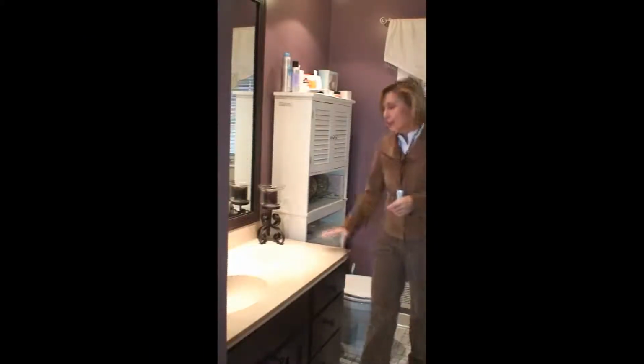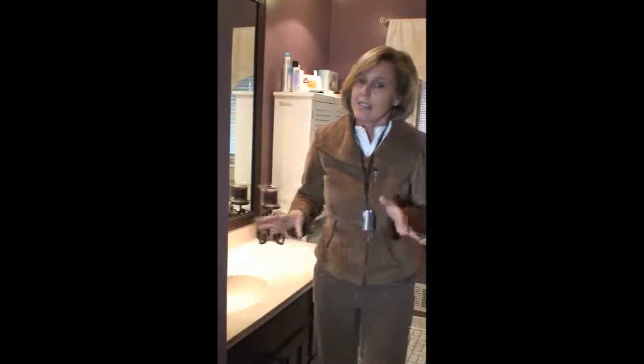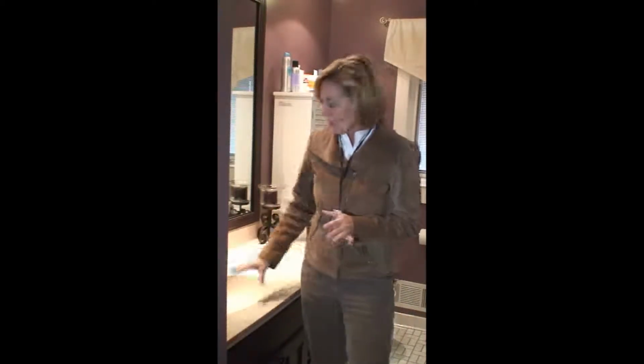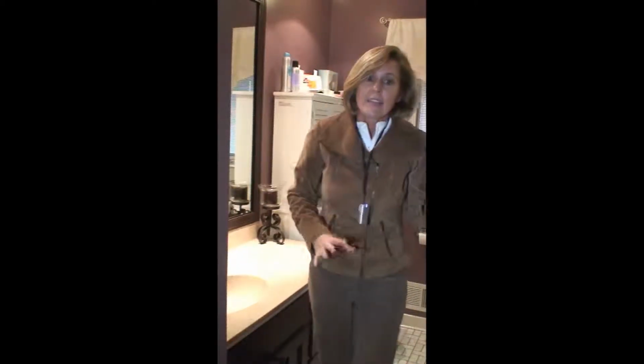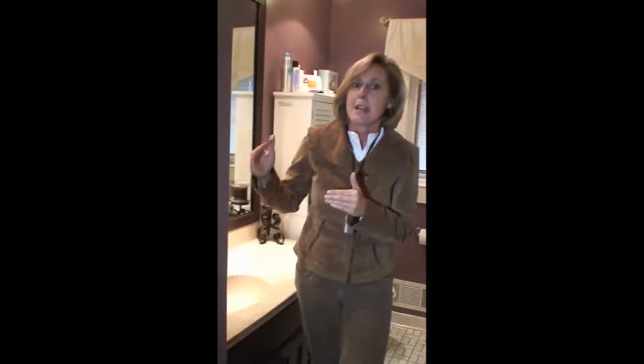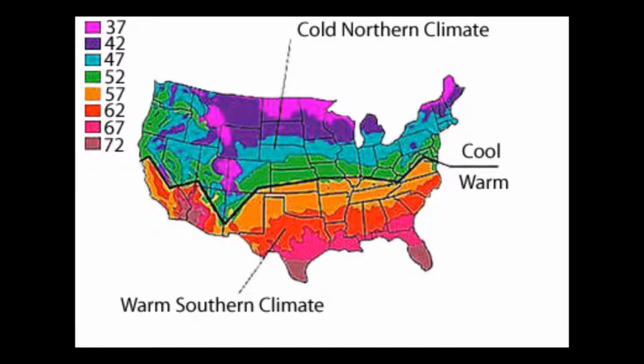One of the biggest considerations of your purchase is where you need hot water. It is important to recognize the number of fixtures that require hot water. Each fixture has a flow rate, like the sink will have one, the toilet will have one, the shower will have one. The flow rate is especially important since tankless water heaters will generate a temperature rise based on the flow rate demanded. Next, you should look at your ambient incoming water temperature.